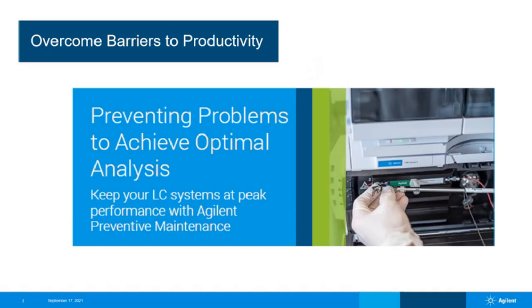An LC system can be used every day or only periodically, shared with a group or individually, and there are many barriers that come up and can limit productivity. You may come into the lab and not know what state the LC is in. How was it left? Who used it last? How old the solvent is? Is it still good? If your system isn't running properly, your data may be unreliable and require troubleshooting or rerunning samples. You really will want to minimize all these barriers and prevent problems to achieve optimal analysis.